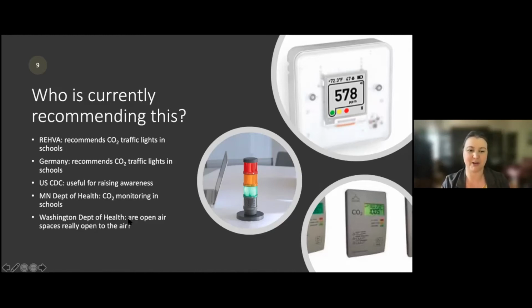The last one I wanted to bring up is the Washington Department of Health, which is probably the best use of the CO2 monitor I've seen so far—ensuring that an open air eating space really is open to the air. As many of us know, it can be very difficult to define a patio, since you can have pony walls, a roof, awnings, plants, shades, and all sorts of things that could block airflow, so it may not be clear if the space really is open to the air. Washington State said: you've got your CO2 sensor, you've got two people seated at the table—if their local CO2 level is more than 450 ppm over 15 minutes, they have to be moved; it's not open to the air. That's a simple and useful approach, because the action point is outdoor air, and that's easy—you know what outdoor air is supposed to be.